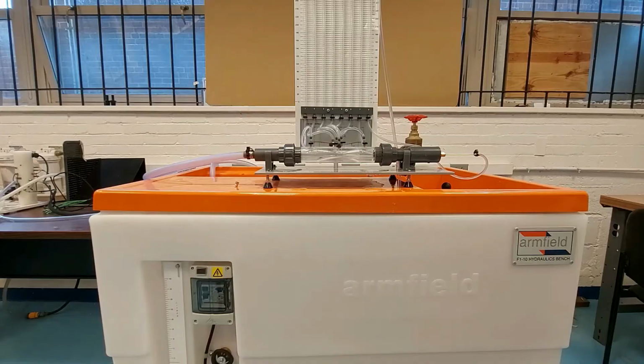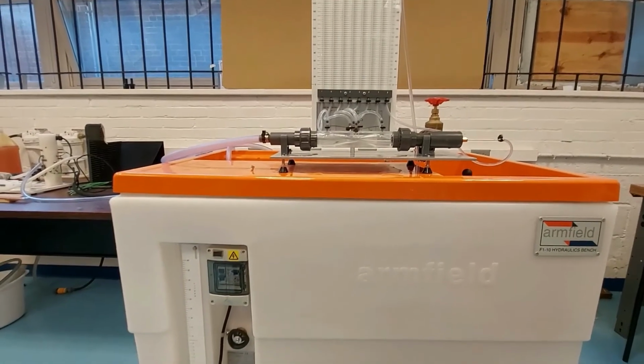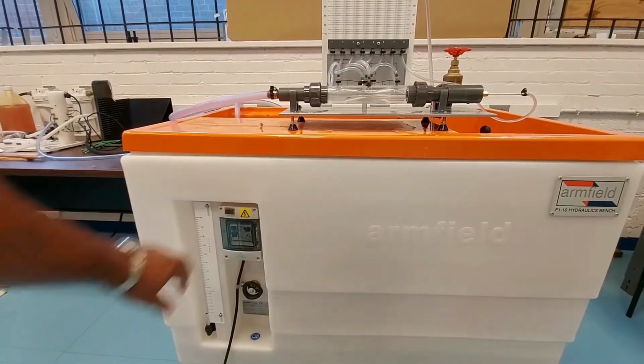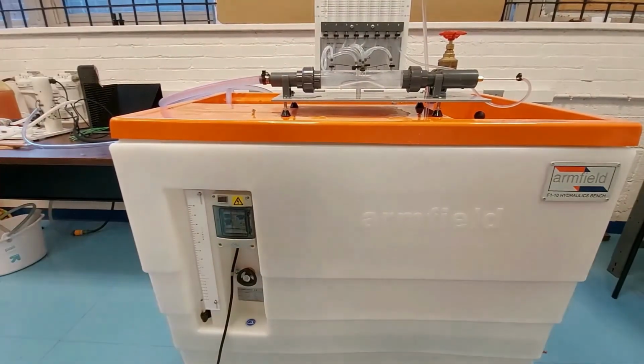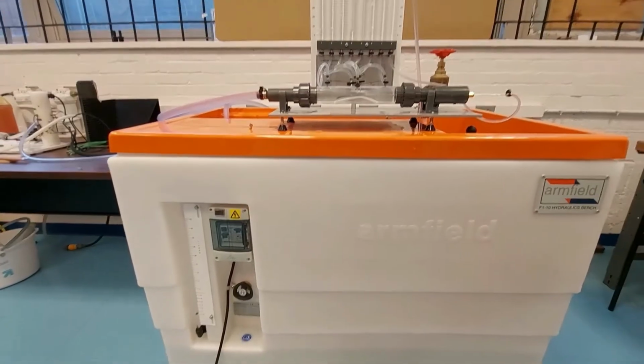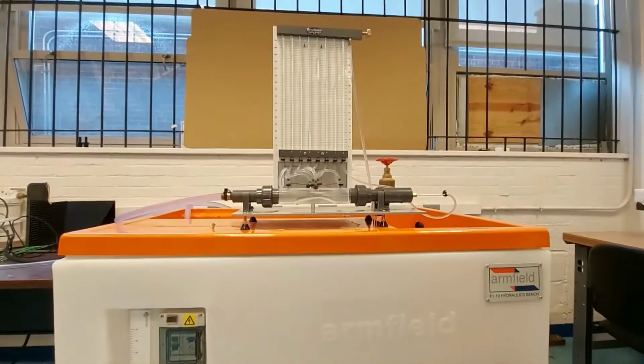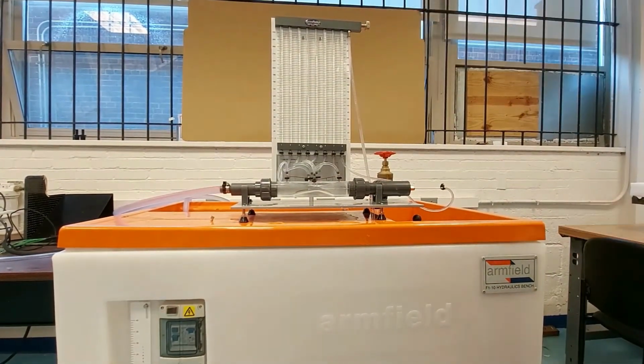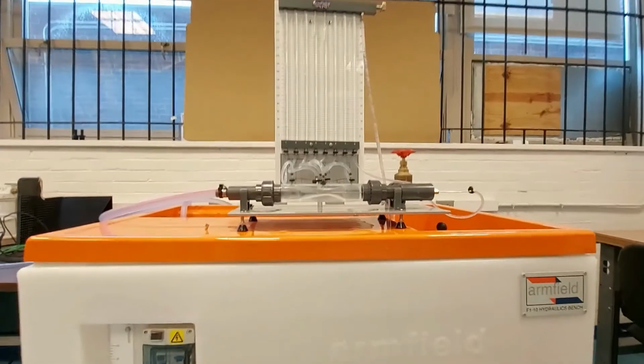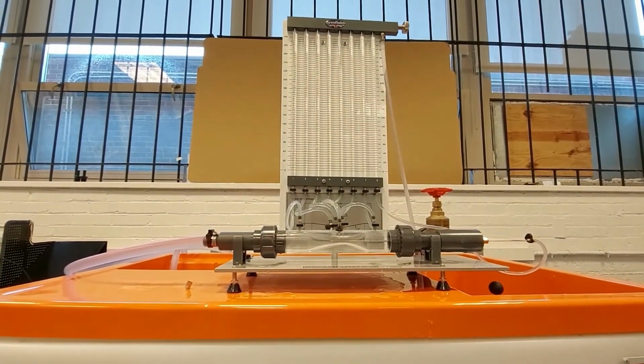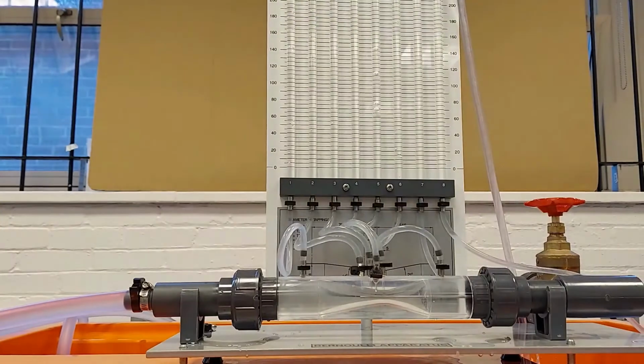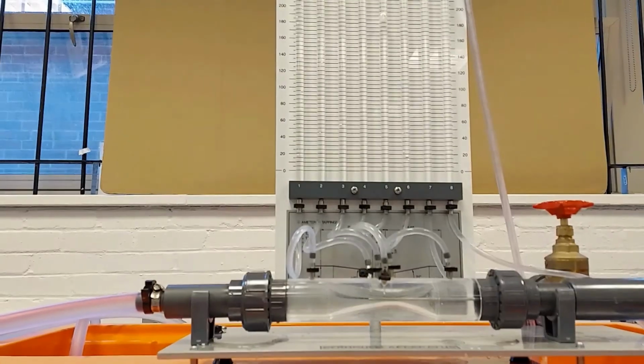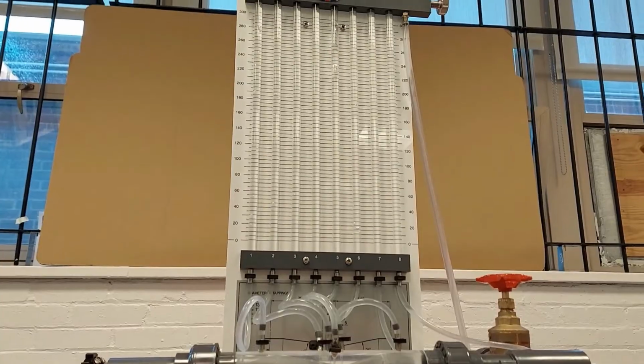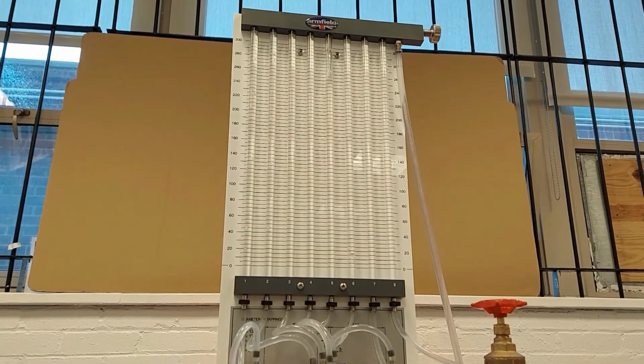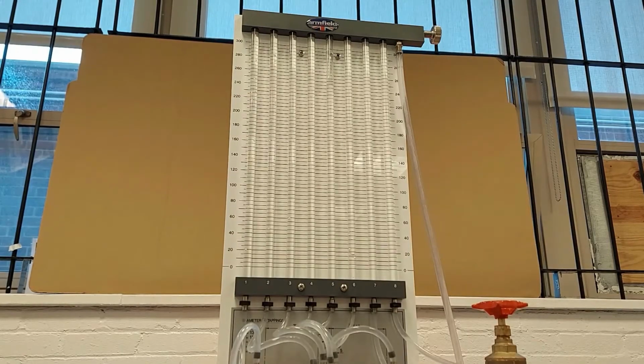Now that our system is leveled, we would then turn the pump on, turn all the valves on, and allow for the system to remove all the air pockets. So as you can see, air bubbles are being removed from the system. We will wait until the system is purged for us to begin the experiment.